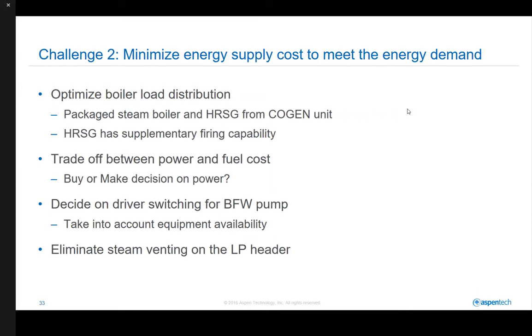Second, in order to adjust operation to minimize energy cost, a number of decisions need to be made on the spot by the plant operators, such as how to allocate steam generations between packaged steam boilers and HRSG to improve steam generation efficiency, make generate or buy decisions on the power utilities to trade off the fuel cost and the power cost, decide whether the boiler feed water pump should be driven by steam turbine or electric motor by taking into account availability of the equipment, and lastly, how to minimize steam venting on the LP header.